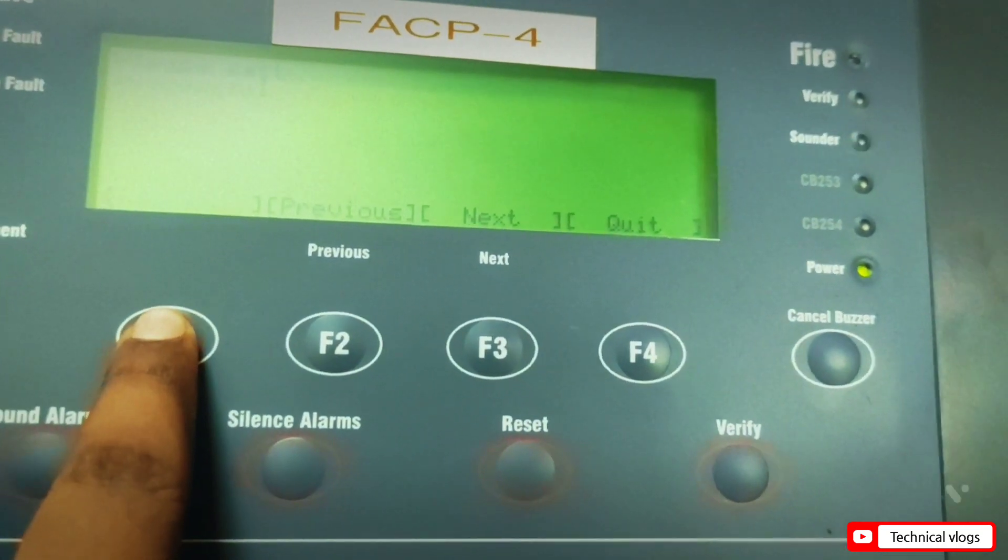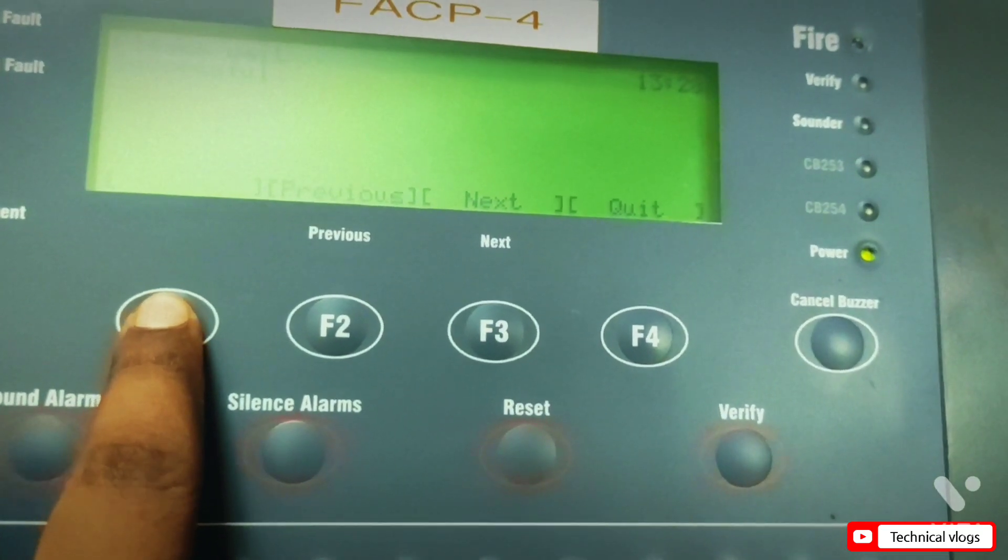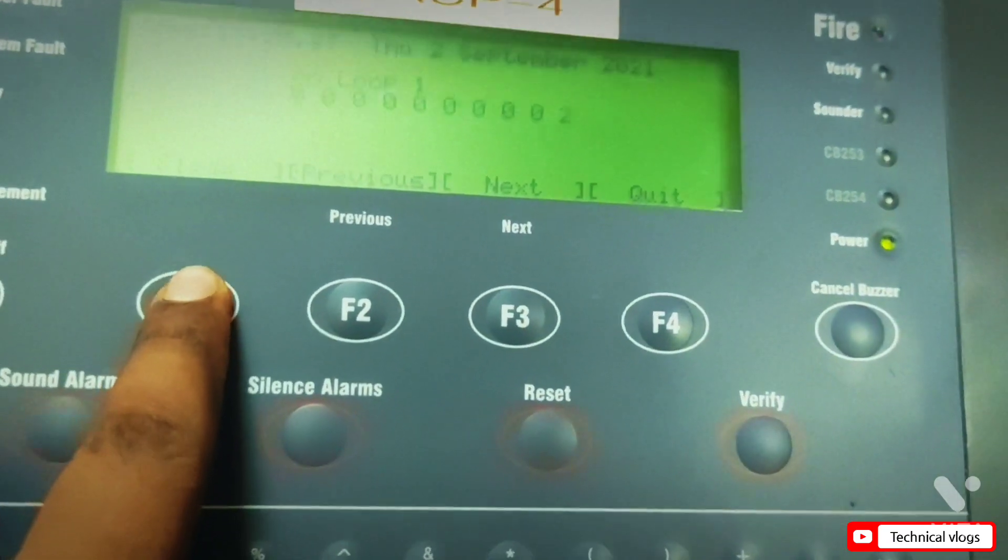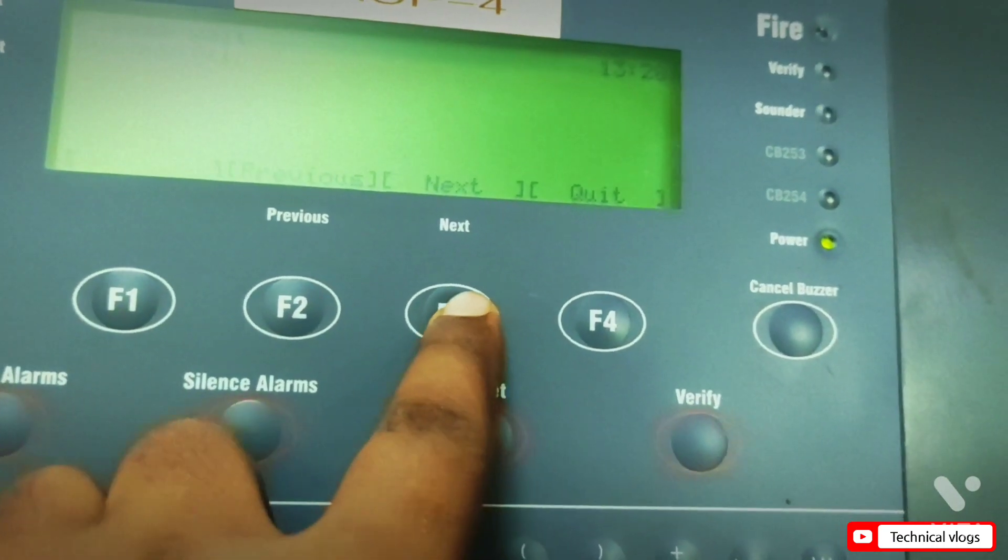If three is present in number value, then it means the sensor of smoke detector is so dirty that it cannot be cleared. In this condition, the smoke detector must be replaced.